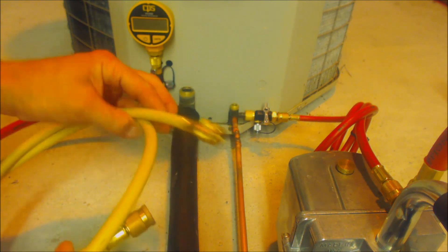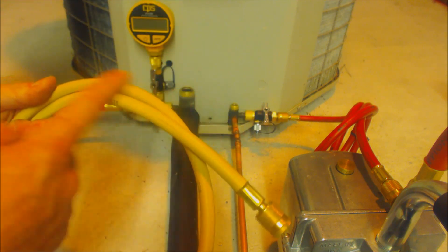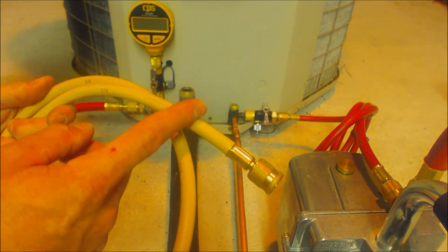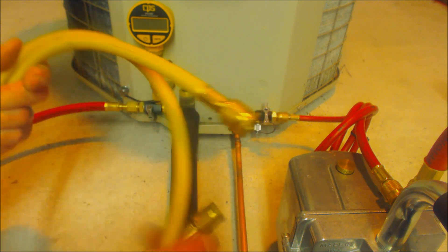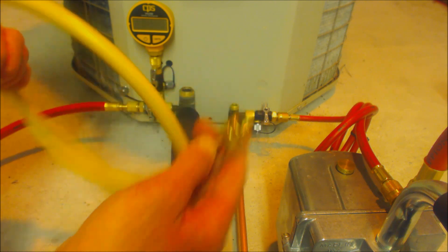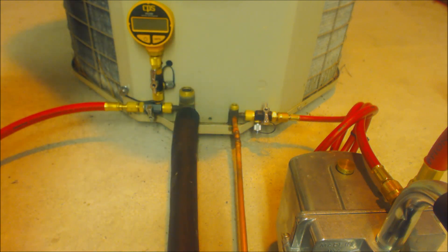So this is what I'm recommending, a hose setup that's also vacuum rated. So these hoses are vacuum rated, not just pressure rated, but they say vacuum rated on them. And you don't have valve core depressors on either side. There are no valves. There's no extra connections. That's what I would recommend you using. The least amount of fittings, the better.